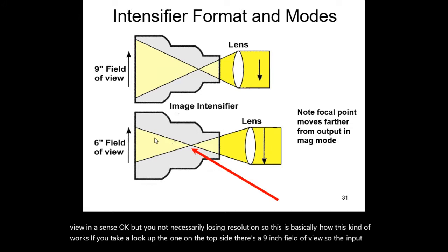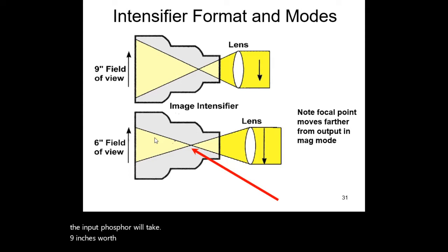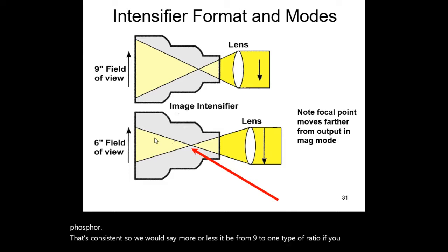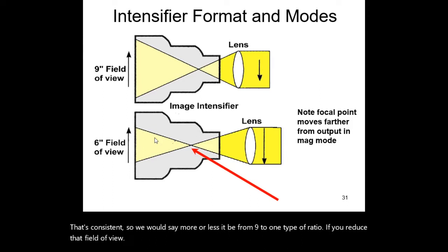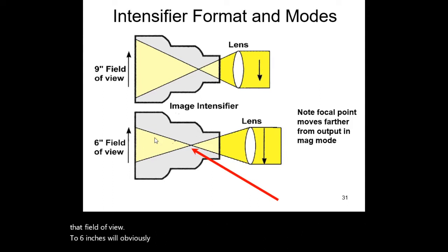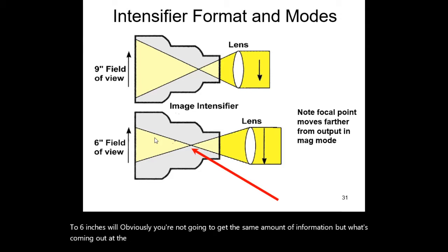So the input phosphor will take 9 inches worth of X-ray field. Now, when it comes over to the output phosphor, that's consistent, so we would say more or less it'd be a 9:1 type of ratio. If you reduce that field of view to 6 inches, obviously you're not going to get the same amount of information, but what's coming out at the other side is the same size, the same field size, but the part, like that arrow, is going to be larger.